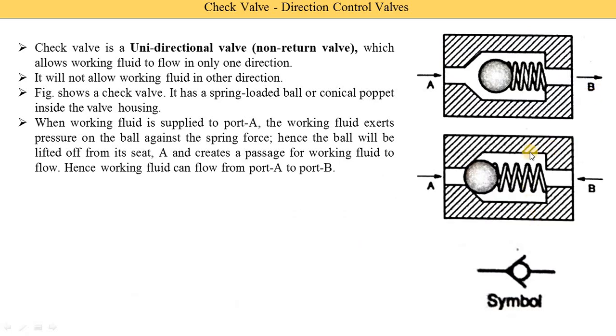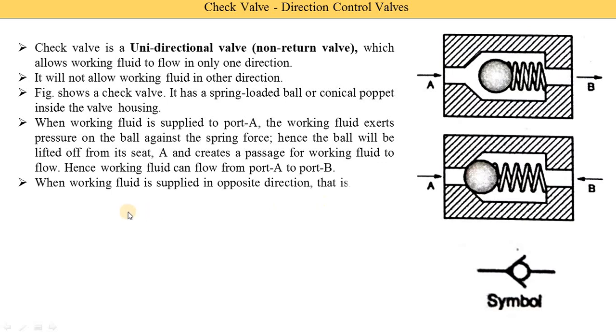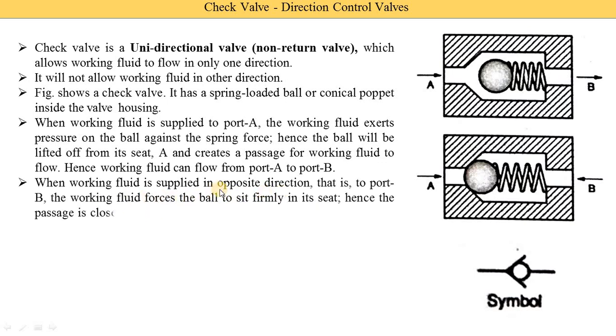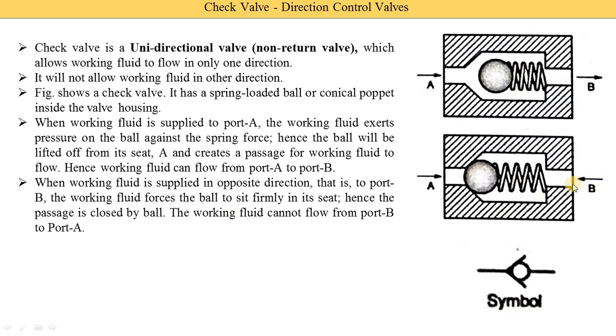The second case is when fluid is coming from port B — the arrow indicates flow toward port B, meaning oil is entering from port B. When the working fluid is supplied in the opposite direction — that is, from port B — the working fluid force causes the ball to sit firmly in its seat. Hence, the passage is closed by the ball and the working fluid cannot flow from port B to port A. The fluid coming from port B applies force on the ball, the ball moves toward its seat, and the passage is closed.